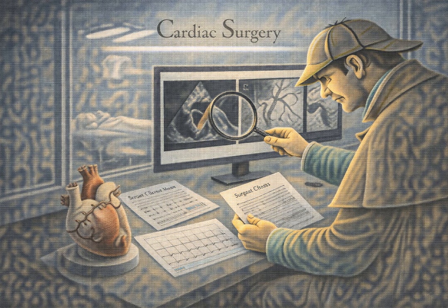First, it goes through the oxygenator. This is your artificial lung. In the early days, they used to just bubble oxygen through the blood, which was actually quite harsh and damaging to the red cells. Right. Modern oxygenators use incredibly fine, hollow fiber membranes. The blood flows on one side, oxygen flows on the other, and gas exchange happens across that membrane, just like in your own lungs. So it's adding oxygen, scrubbing out the carbon dioxide.